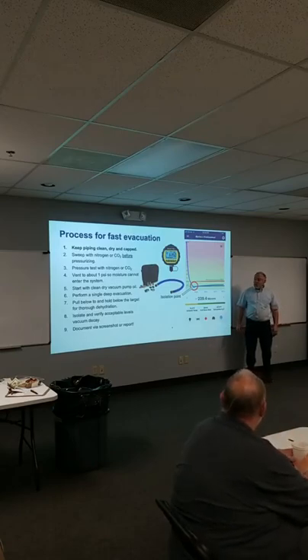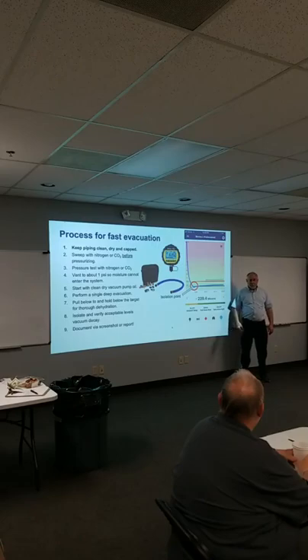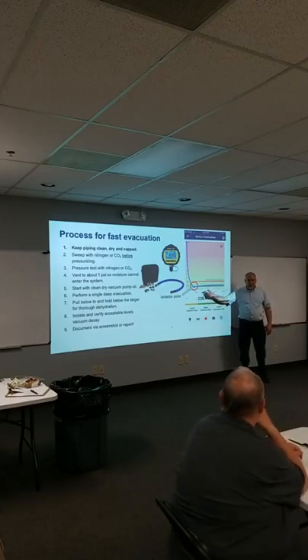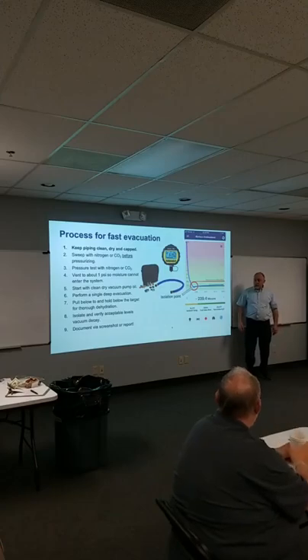Went out to do the video with FieldPiece, and it came down so fast that I had the videographer stop the video and say, there's something wrong here. There's just no way this happened. I had to go, get the tank of nitrogen, we purged it again. Because we're literally taking vacuums that took an hour, and we're taking it down to less than 1 minute. We're less than 2 or 3 minutes, you're down south of 200 microns, okay? This is what we forgot as an industry, is just how to do this stuff.